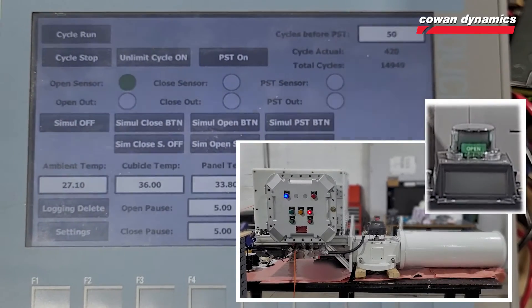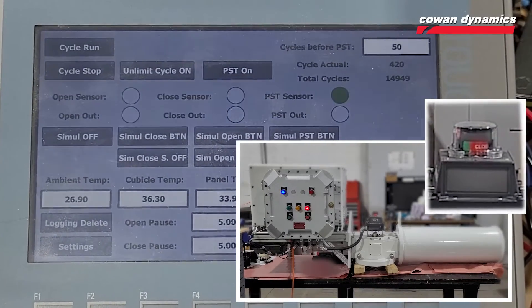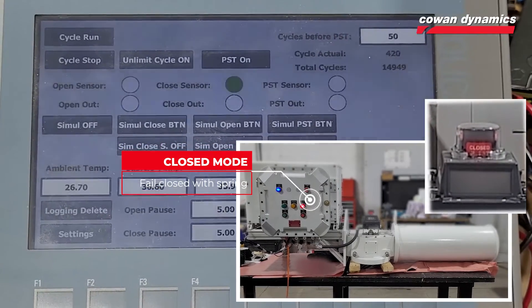Once the unit is fully opened, the system simulates a failure via an ESD signal, releasing the hydraulic pressure in the actuator, allowing the compressed spring to complete the clockwise — or in this case, close — stroke.